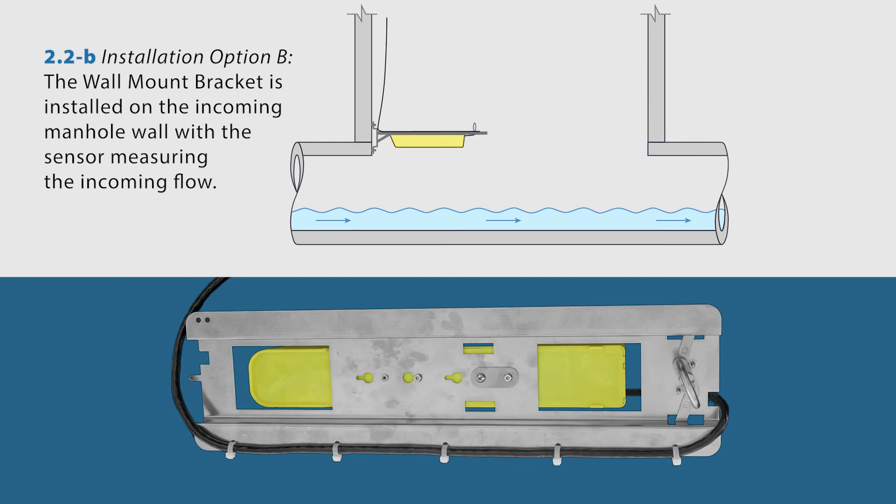When the wall mount bracket is installed on the incoming manhole wall, with the sensor measuring the oncoming flow, thread the sensor cable through the notch on the loop end of the sensor bracket and cable tie the sensor cable to the bracket using the five holes along the edge of the sensor bracket.